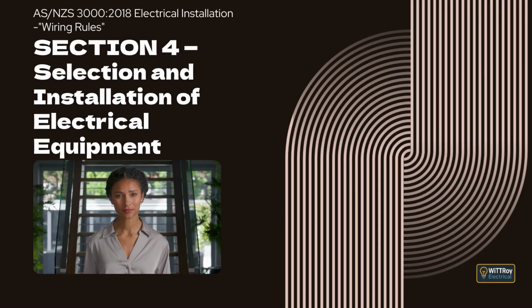Clause 4.10.5, Additional protection. This clause explains that all heating cables must be provided with additional protection by an AS/NZS RCD with a rated residual current not exceeding 30 mA. It explains that where heating units have a conductive covering, that covering must be earthed. It explains that where underfloor heating units do not have a conductive covering, an earthed metallic grid with spacing not exceeding 30 mm must be installed above the heating cable. It also explains that all heating units must be provided with sufficient mechanical protection to prevent damage.